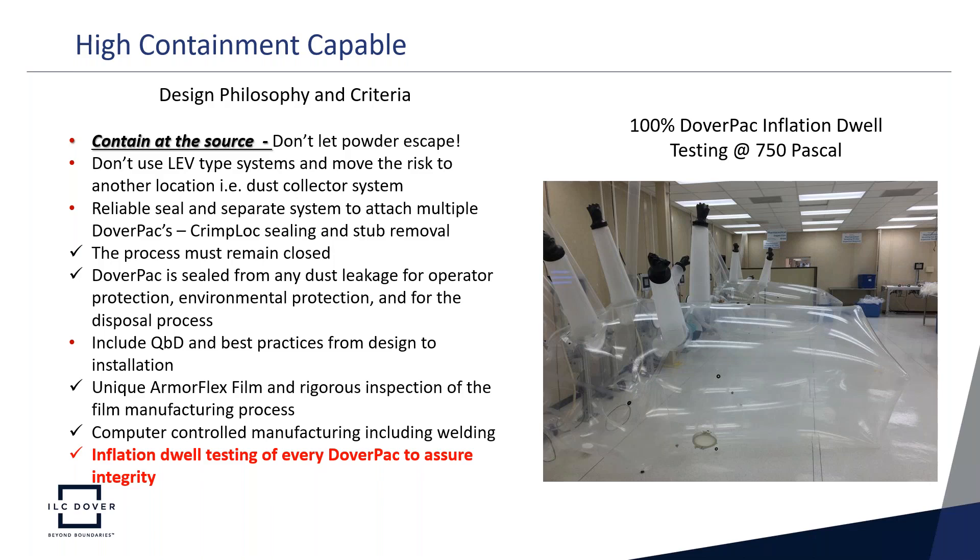In the design philosophy and criteria, quality-by-design ideas and best practices were applied from design through installation. The DoverPac uses the unique ArmorFlex film with rigorous inspection of the film and manufacturing processes. Processes are computer-controlled, with particular attention to computer-controlled welding. The final step is inflation-dwell testing of every DoverPac at 750 pascals to assure integrity. Hundreds of thousands of units have passed this test successfully.